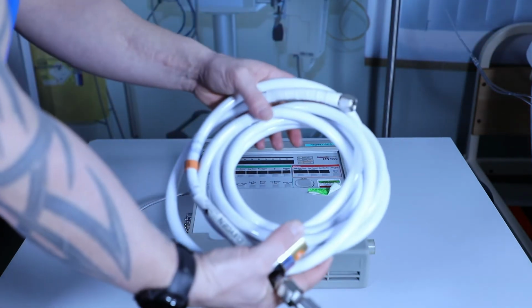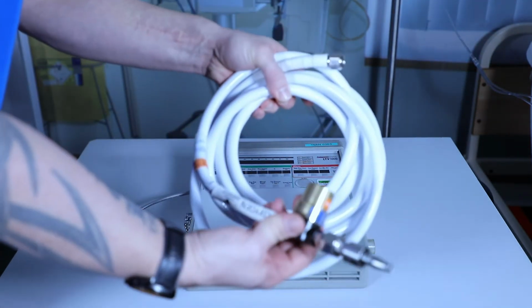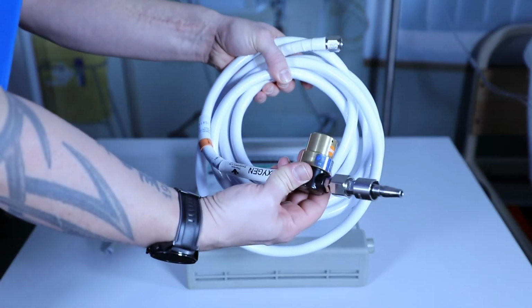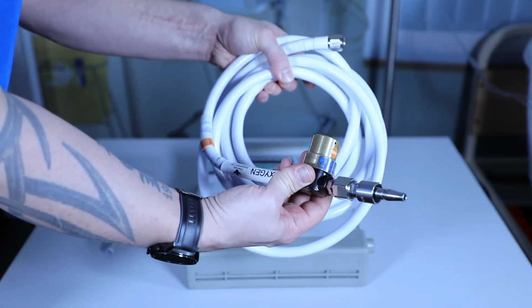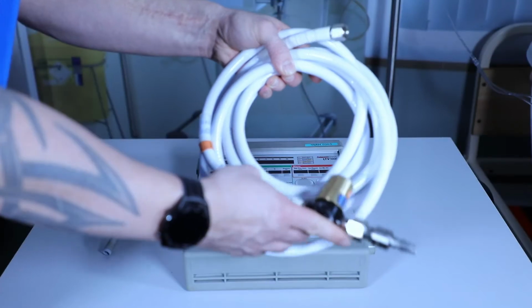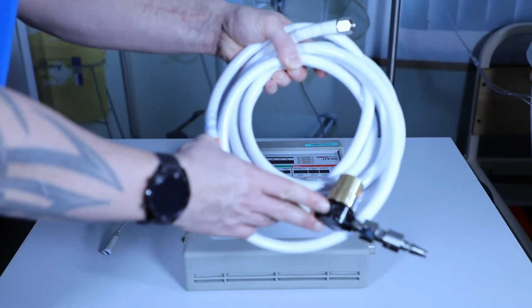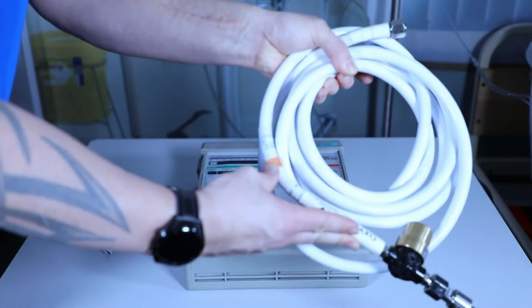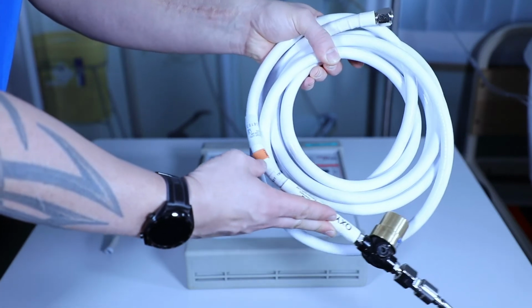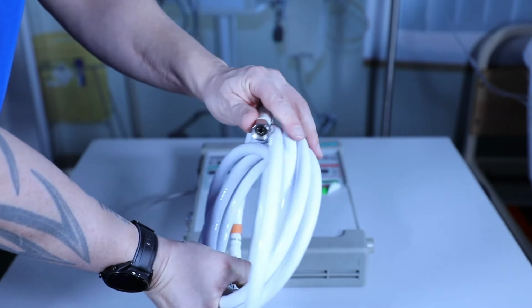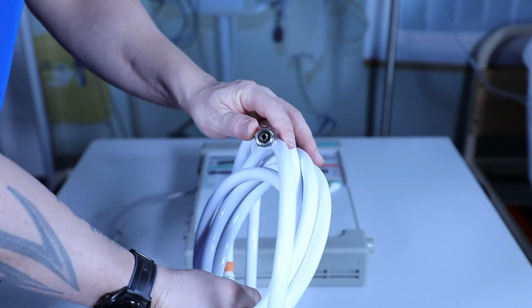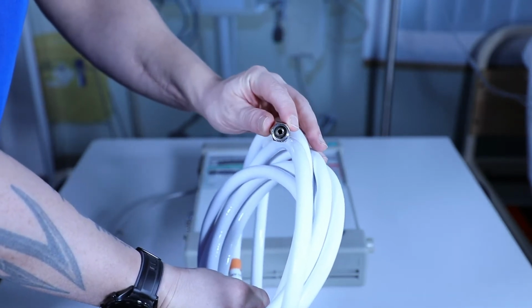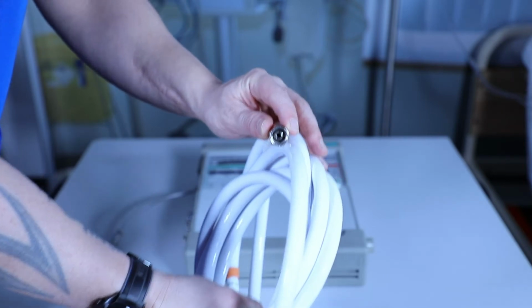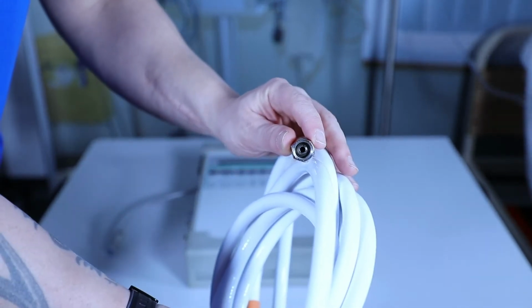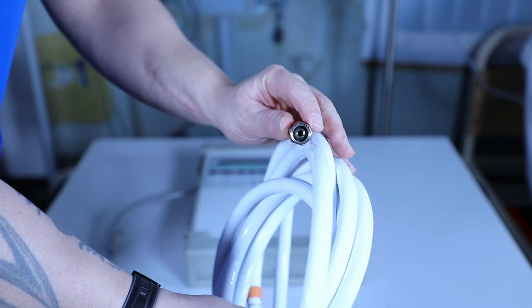The next component we're going to inspect is the high pressure O2 hose. This should come in its own carry bag, which isn't present here. We want to pay particular attention to the regulator. We also need to note the expiry date. This is usually displayed on a rubber band on the hose itself, in this case the orange one. The hose expires after 4 years. The most important thing about the O2 hose is to ensure that the integrity of the black O-ring, which you may be able to see here, is actually intact.